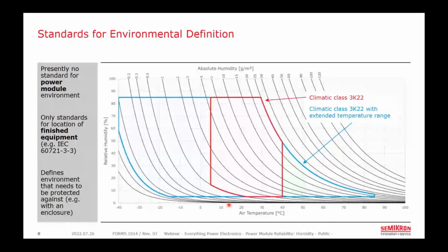Lastly, since most electrical components are designed for a larger temperature range than this 5 to 40 degrees Celsius that you see here, we can extend that to a more common negative 40 degrees to plus 85 degrees temperature window, while we're still adhering to these limits for absolute humidity to get this blue curve shown here. And this is used with more integrated power electronics assemblies, such as the intelligent power module, like the SKiiP product that we have, which is intended to be installed in a location defined as a 3K22 climatic class with a quote unquote extended temperature range.